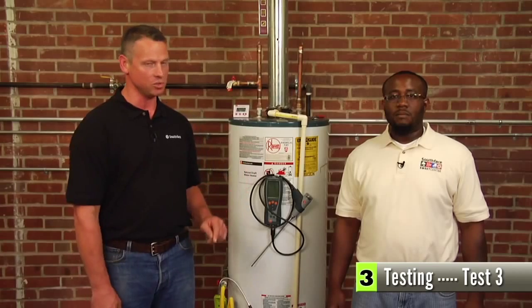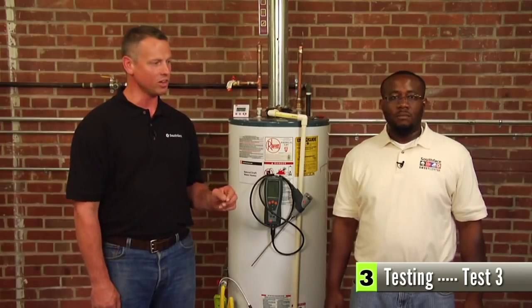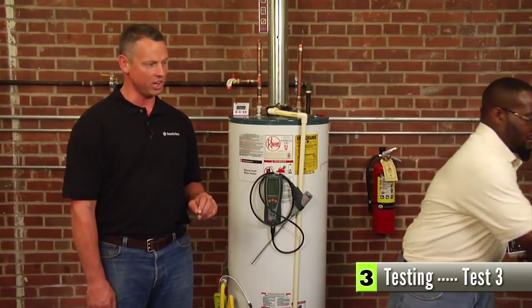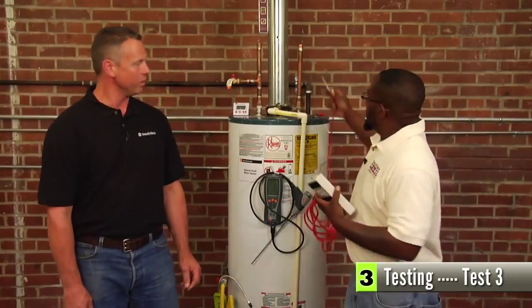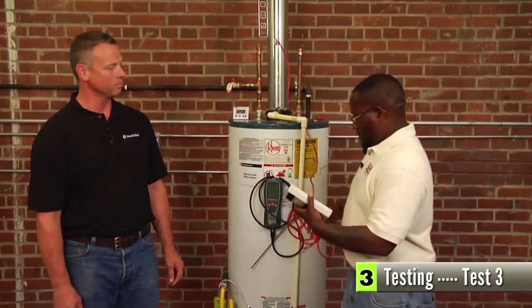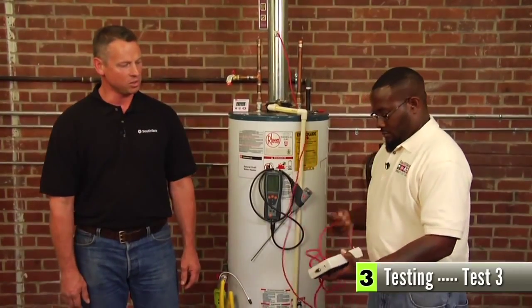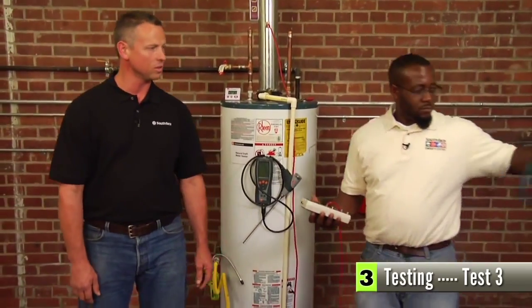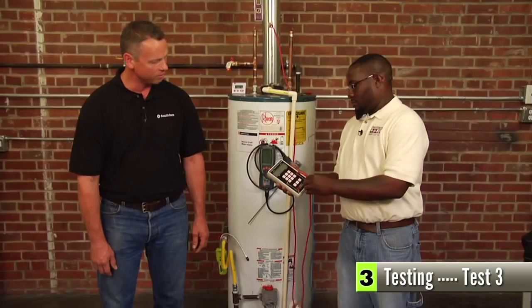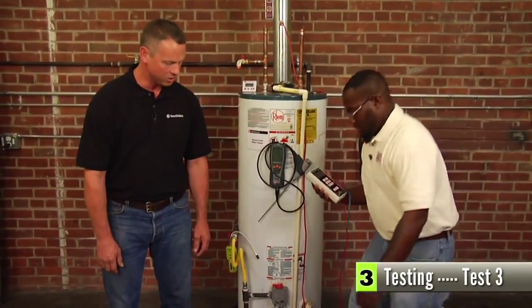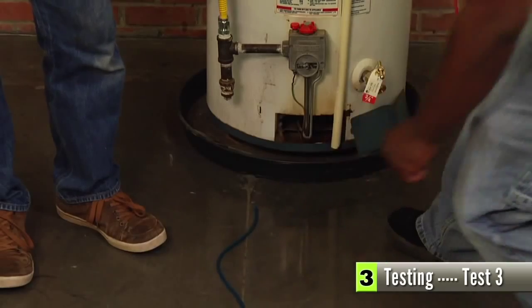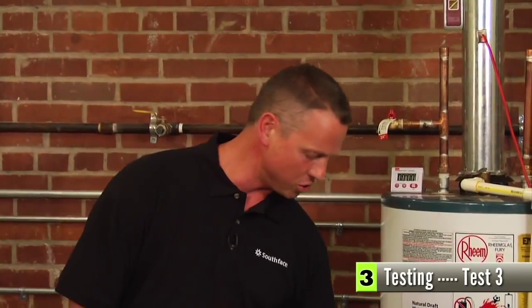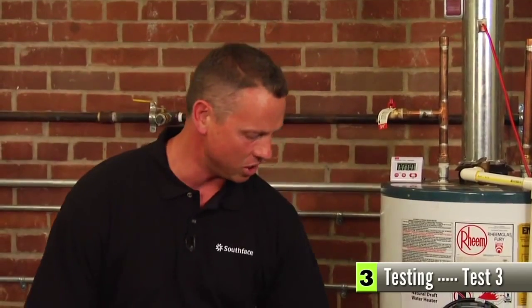This CAS was large enough to stand in with the door closed, so we only needed 1 gauge hose. Now, if this had been too small for us to fit in, then we need 2 hoses. We'll use one connected to the static pressure probe on the input side, and we'll go ahead and insert the static pressure probe into the flue. Connect that hose to the input on our DG700, and then we'll use a reference hose on the same side of the DG700 to fit inside our CAS. And now we've got flue pressure with reference to the CAS, and this is inside the CAS with the door closed.